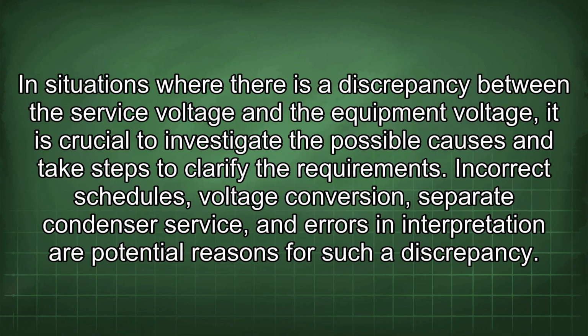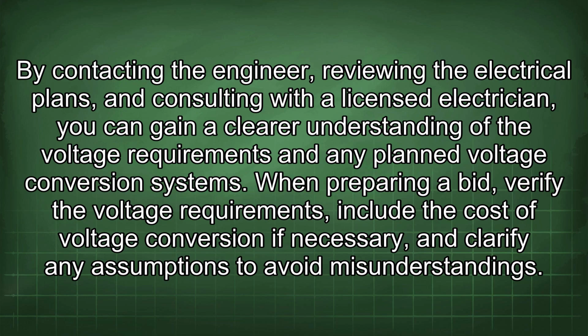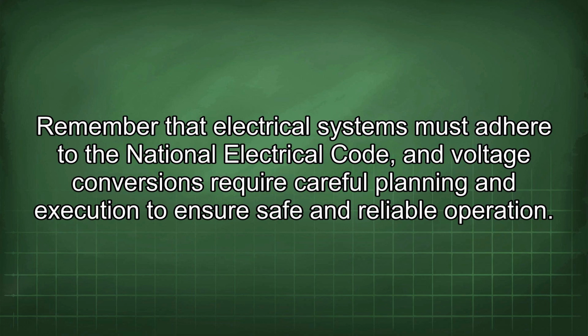In situations where there is a discrepancy between the service voltage and the equipment voltage, it is crucial to investigate the possible causes and take steps to clarify the requirements. Incorrect schedules, voltage conversion, separate condenser service, and errors in interpretation are potential reasons for such a discrepancy. By contacting the engineer, reviewing the electrical plans, and consulting with a licensed electrician, you can gain a clearer understanding of the voltage requirements and any planned voltage conversion systems. When preparing a bid, verify the voltage requirements, include the cost of voltage conversion if necessary, and clarify any assumptions to avoid misunderstandings. Remember that electrical systems must adhere to the National Electrical Code, and voltage conversions require careful planning and execution to ensure safe and reliable operation.